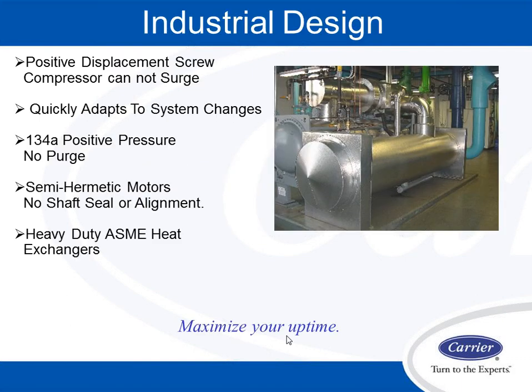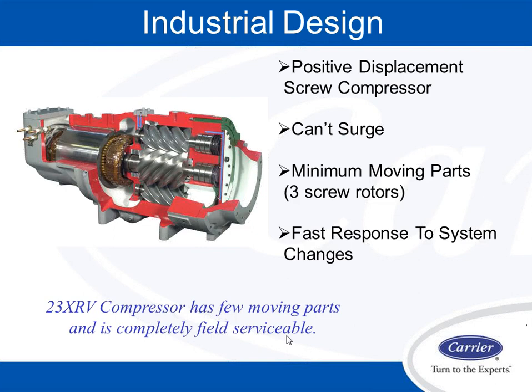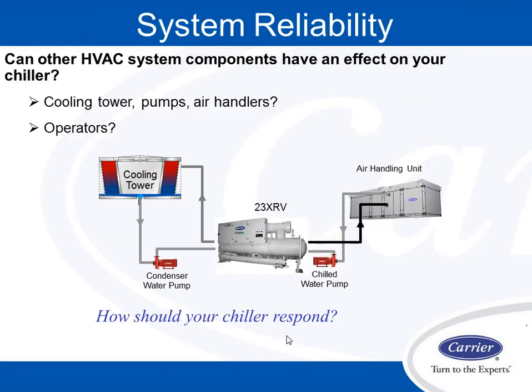Again, industrial design. Positive displacement, so the machine cannot surge, and it quickly adapts to system change. We'll show you that in a bit. R-134a, no purge. Semi-hermetic motor. It's not an open drive motor like an open drive centrifugal manufacturer produces, so I have no shaft seal or shaft seal alignment issues. And the cooler and condensers are ASME pressure vessels. Again, positive displacement, can't surge, 3 moving parts, very fast response.